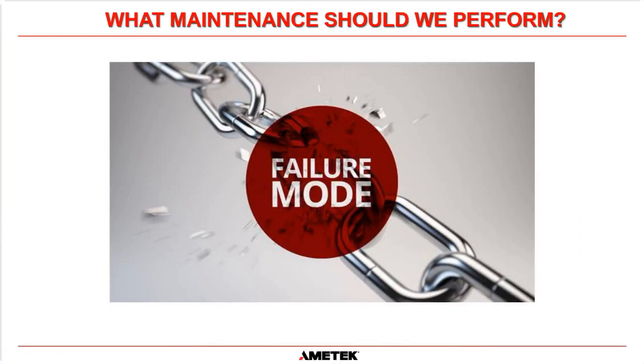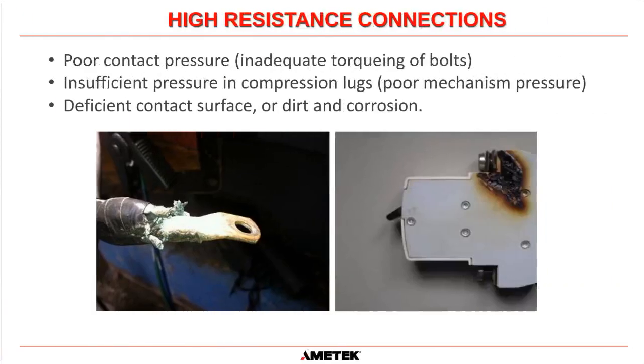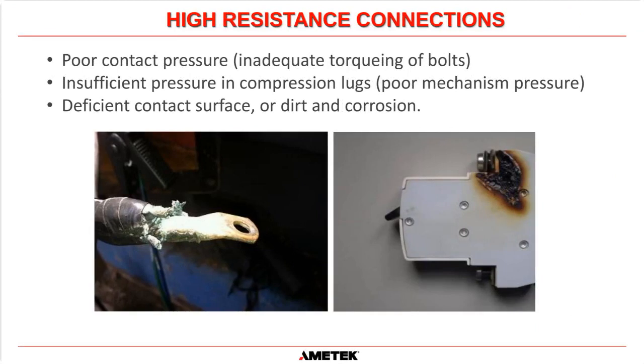Okay, so what are the most common failure modes with UPSs and electronics in general? Well, the first one is high resistance connections, and that can be from poor contact pressure, in other words, inadequate torquing of bolts. It can be from insufficient pressure in compression lugs, and what that means is that the lug has not been compressed correctly. You know, the strands of the wires going into the lug have either been cut.